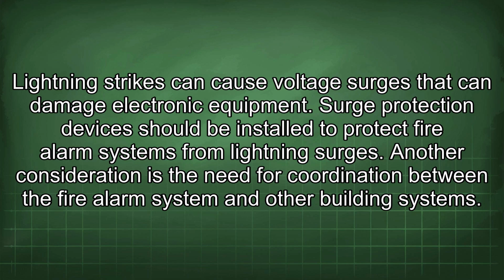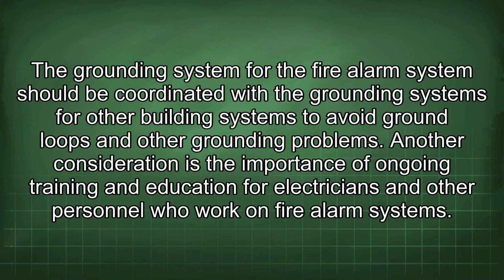Another consideration is the need for coordination between the fire alarm system and other building systems. The grounding system for the fire alarm system should be coordinated with the grounding systems for other building systems to avoid ground loops and other grounding problems.